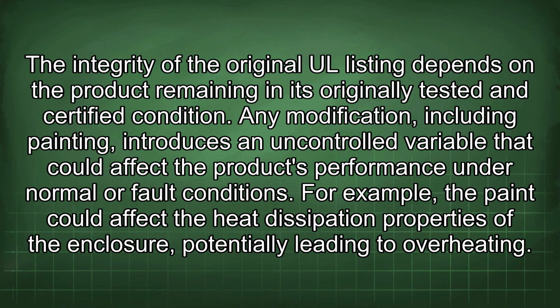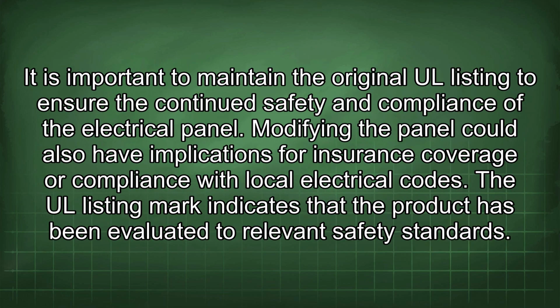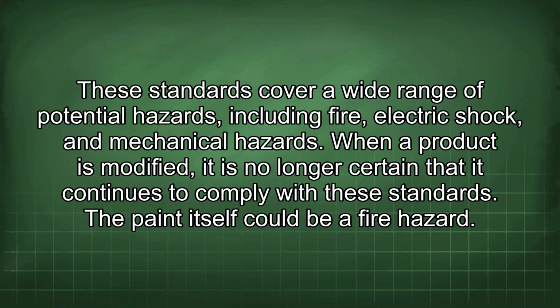For example, the paint could affect the heat dissipation properties of the enclosure, potentially leading to overheating. It is important to maintain the original UL listing to ensure the continued safety and compliance of the electrical panel. Modifying the panel could also have implications for insurance coverage or compliance with local electrical codes. The UL listing mark indicates that the product has been evaluated to relevant safety standards. These standards cover a wide range of potential hazards, including fire, electric shock, and mechanical hazards.